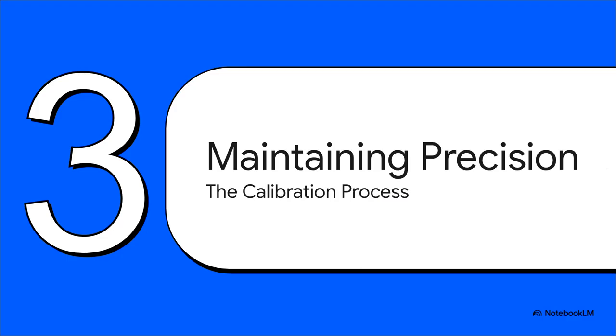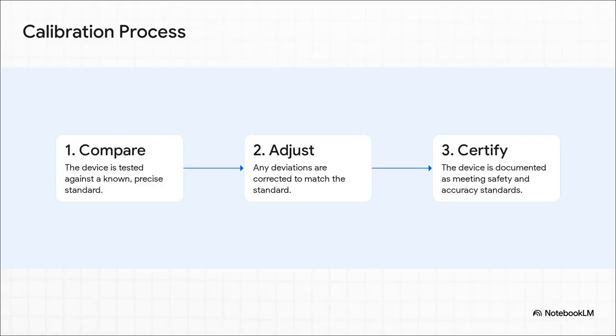Okay, so this precision is obviously important, but how is it actually maintained? Well, it's not magic. It's a very meticulous, repeatable process that builds a system of trust, one device at a time. It really all boils down to these three key steps. First, you compare. You take a device, let's say a lab centrifuge, and you test it against a master standard that's known to be perfect. Second, you adjust. If it's spinning a little too fast or a little too slow, a technician fine-tunes it until it matches that standard exactly. And finally, and this part is vital, you certify it.